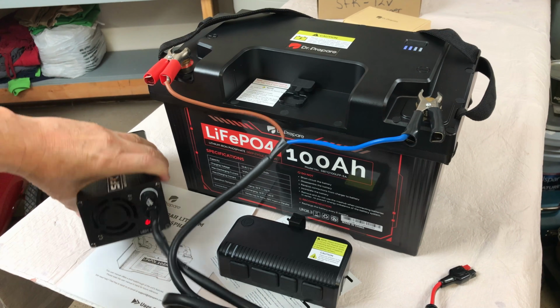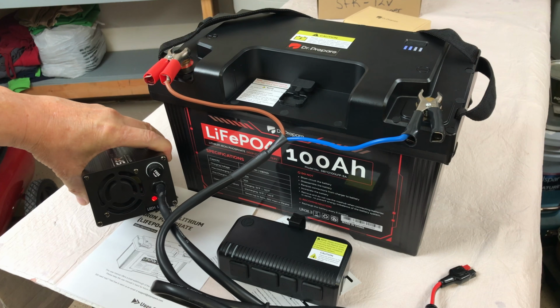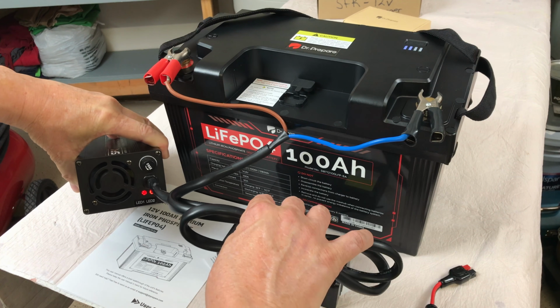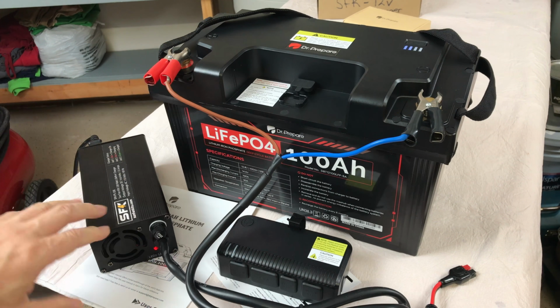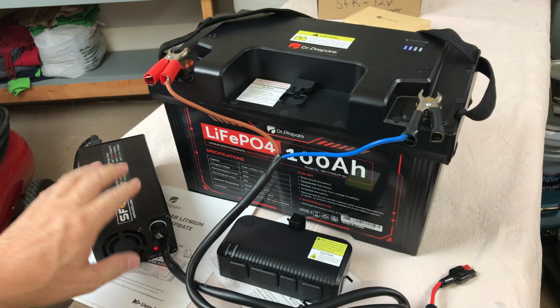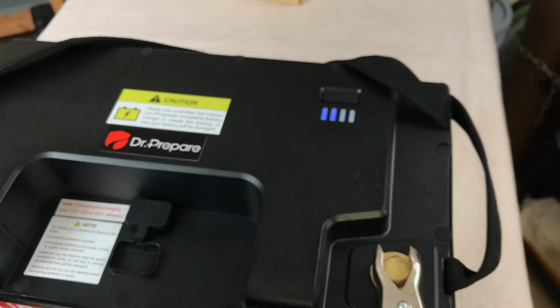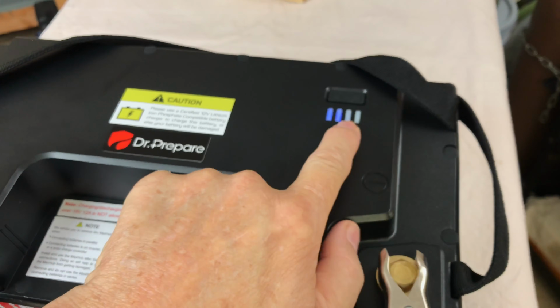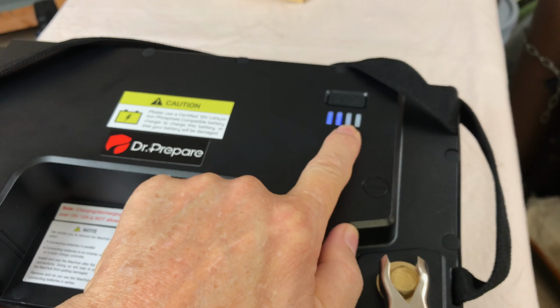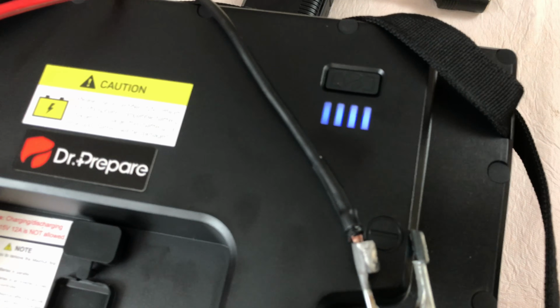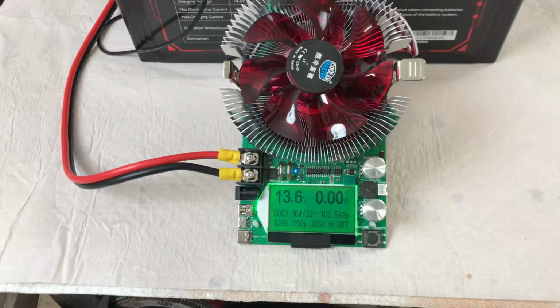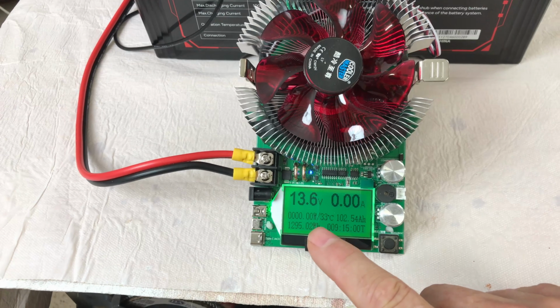Okay, I've got the 25 amp SFK charger on there. Two red lights means we're charging, and it'll turn green when it's done. So we'll let it go ahead and charge up. I noticed that the charge indicator during the charge is kind of blinking on the 3/4 light there. Now showing 4 bars, so it's completely charged. And I've got it set up for a discharge capacity test.